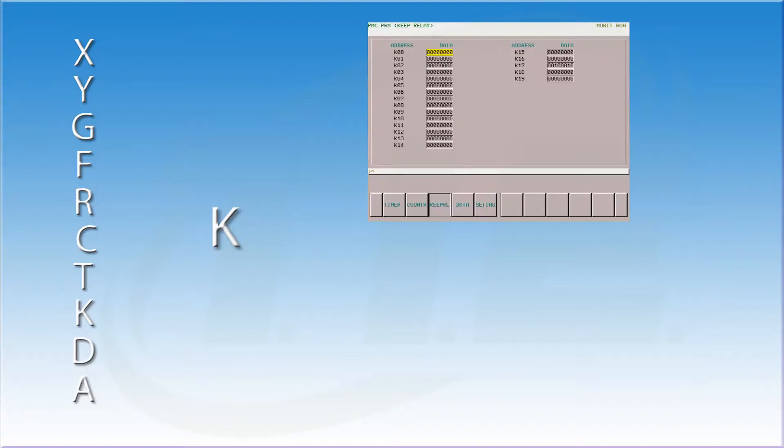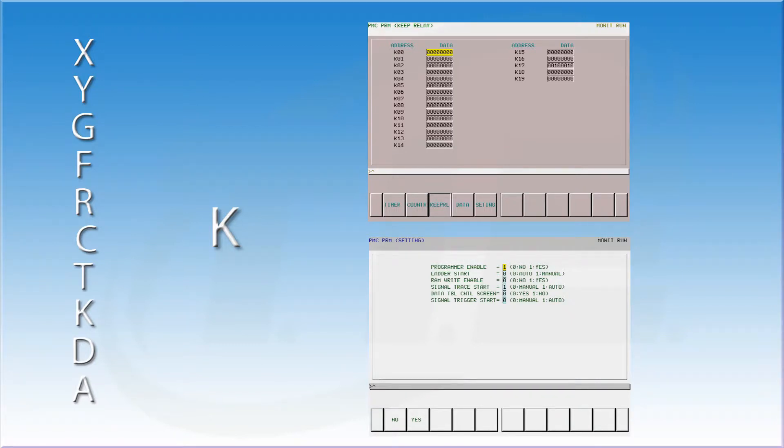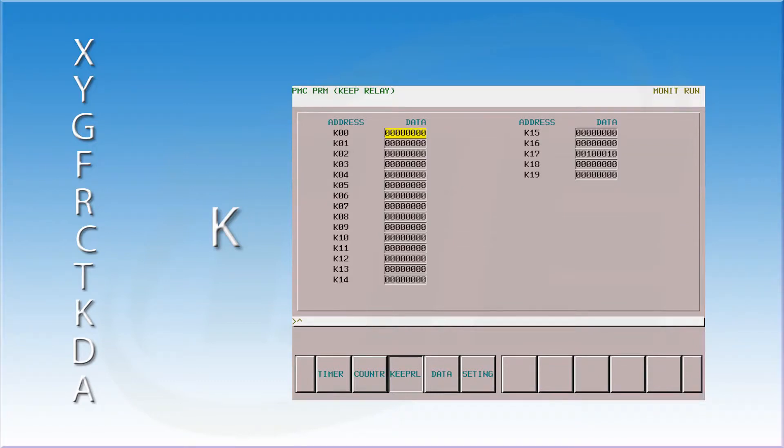K addresses are keep relays. They serve several functions. One is to turn on or off various settings in the PMC control. These settings relate to items such as how the PMC starts up, the display of certain screens related to inputting and outputting information about the PMC, and certain diagnostic functions. A keep relay is set by going to a keep relay data table. The information is stored as a binary pattern. Once the keep relay is set, the control will remember its last state, a one or a zero. When the power to the machine is turned off and back on again, the PMC will look at the keep relay table and set the appropriate contacts high or low.